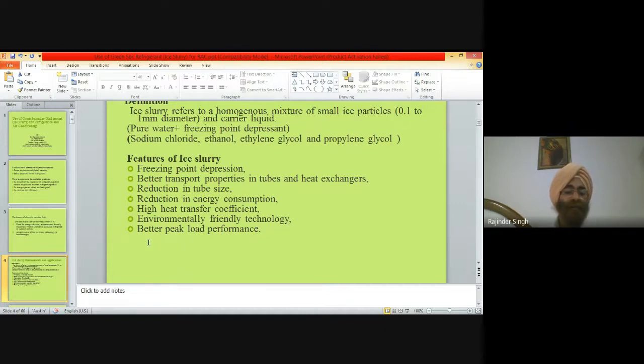Now, better peak load performance, which is very important for any nation. For example, in peak summer the ambient temperature is around 44-45 degrees C, and electricity demand is very high, sometimes causing the grid to trip due to heavy load. What we do is produce ice slurry during off-peak hours, such as at night, store it, and use it during the day when demand is high. This reduces the load on our grid and eliminates the chance of grid tripping. This is a very important feature of ice slurry in thermal storage systems.